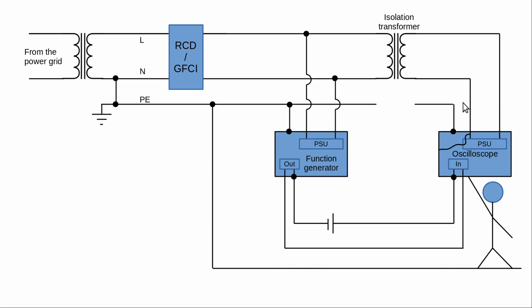And it also doesn't matter which side has this fault condition, as long as not both of them have the fault. So that's why we use an isolation transformer. Now nothing can happen to you as you operate the device, and you can have any difference between those two grounds as you want.